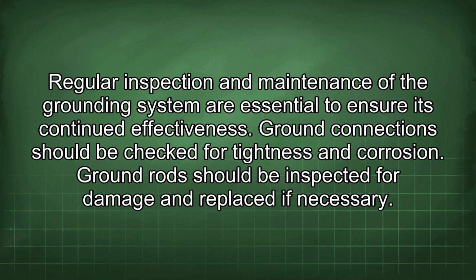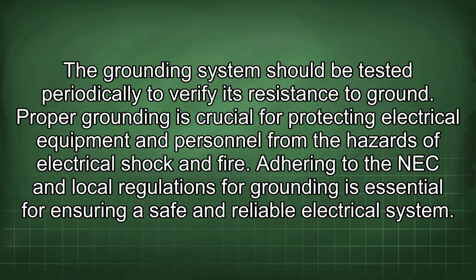Regular inspection and maintenance of the grounding system are essential to ensure its continued effectiveness. Ground connections should be checked for tightness and corrosion. Ground rods should be inspected for damage and replaced if necessary. The grounding system should be tested periodically to verify its resistance to ground. Proper grounding is crucial for protecting electrical equipment and personnel from the hazards of electrical shock and fire. Adhering to the NEC and local regulations for grounding is essential for ensuring a safe and reliable electrical system.